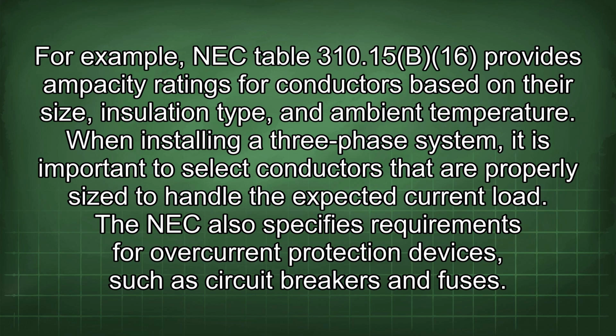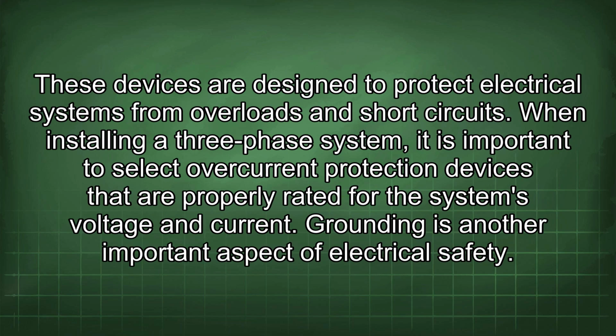When installing a three-phase system, it is important to select conductors that are properly sized to handle the expected current load. The NEC also specifies requirements for overcurrent protection devices, such as circuit breakers and fuses. These devices are designed to protect electrical systems from overloads and short circuits. When installing a three-phase system, it is important to select overcurrent protection devices that are properly rated for the system's voltage and current. Grounding is another important aspect of electrical safety.